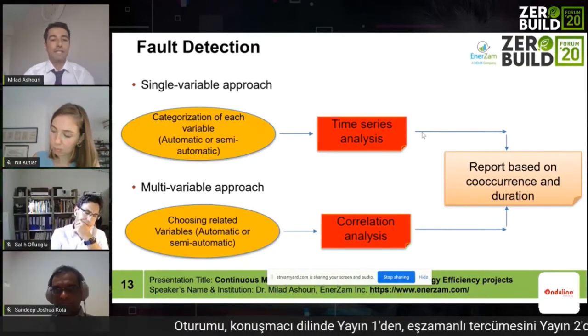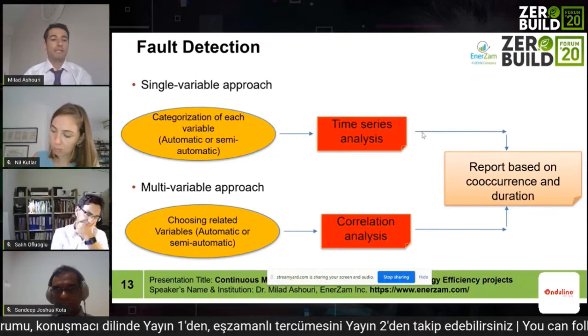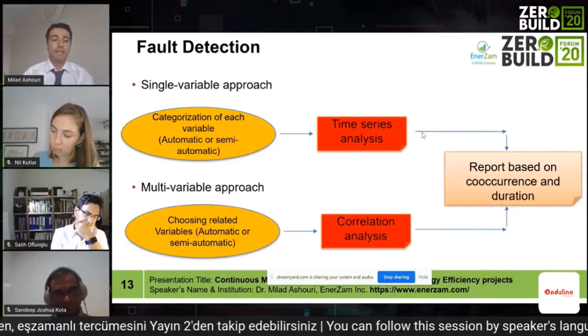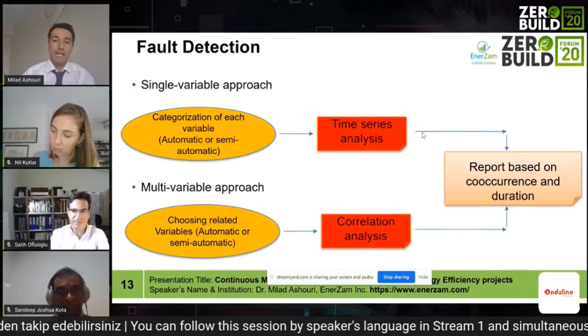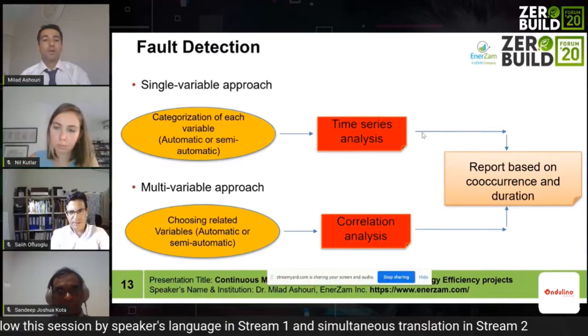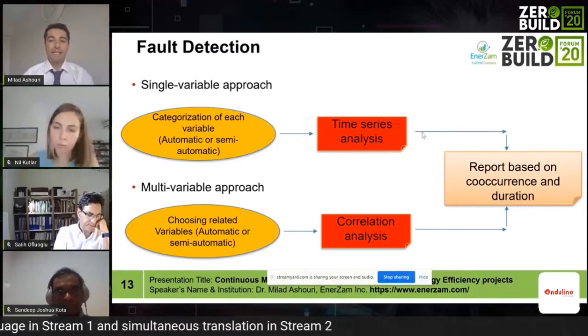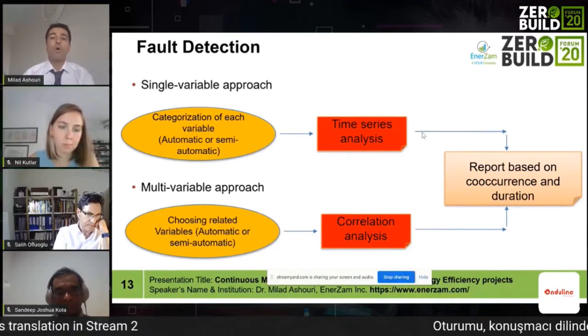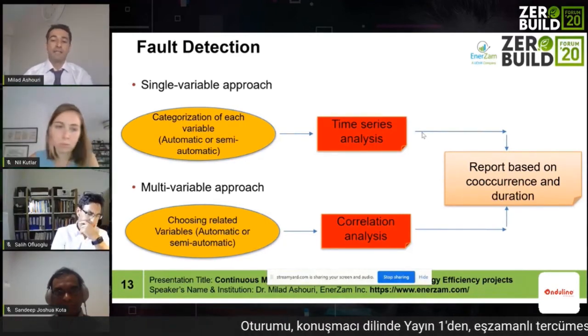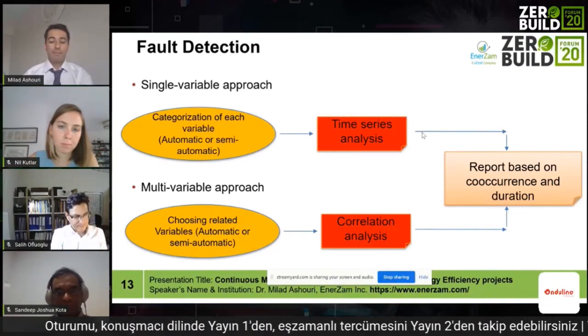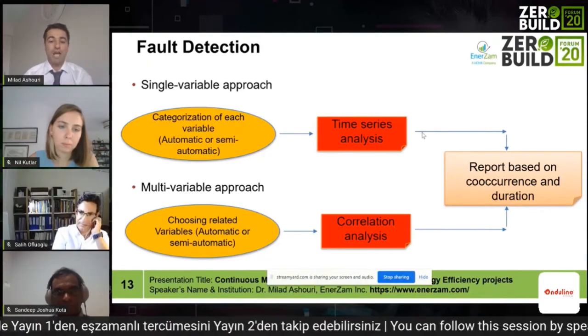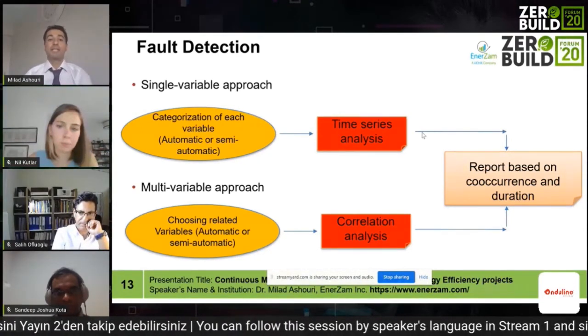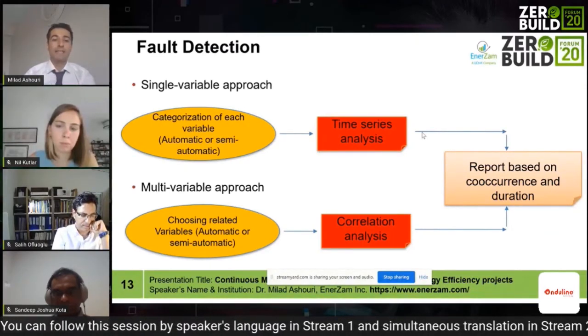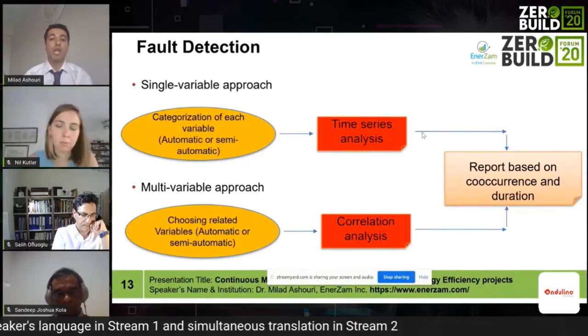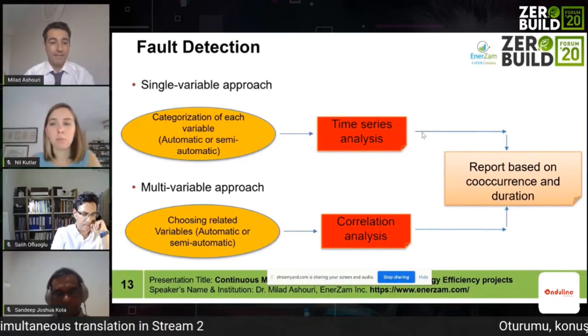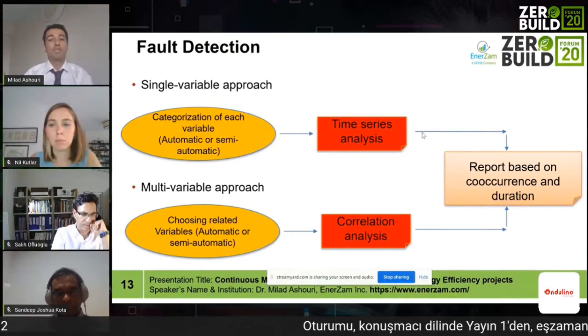In fault detection, we have a single variable approach and a multivariable approach. Single variable means we take one variable in a building, apply time series analysis, and find the times the data shows anomalous behavior as opposed to normal behavior, then report based on co-occurrence and duration. But a building HVAC system has a synergy effect, meaning whenever something goes wrong, or is far from the design, it shows up through many variables because they are all interconnected.